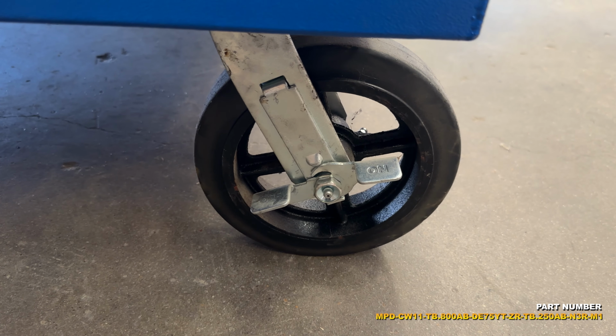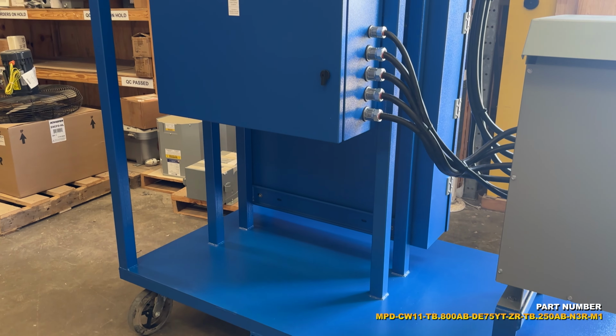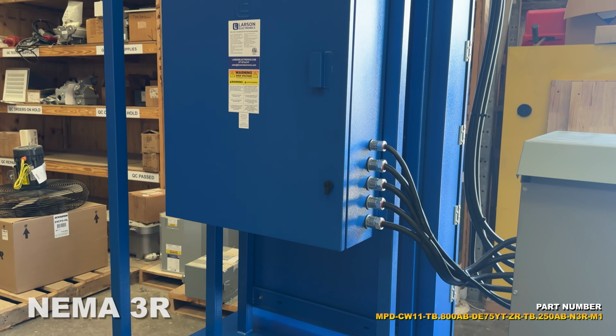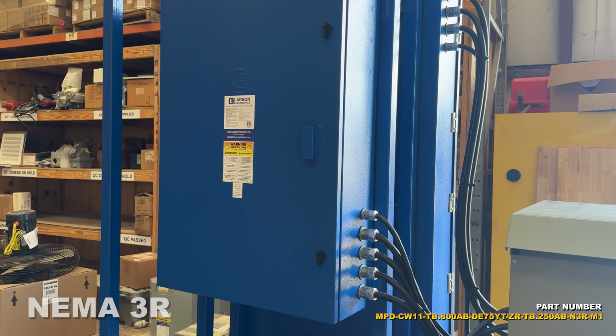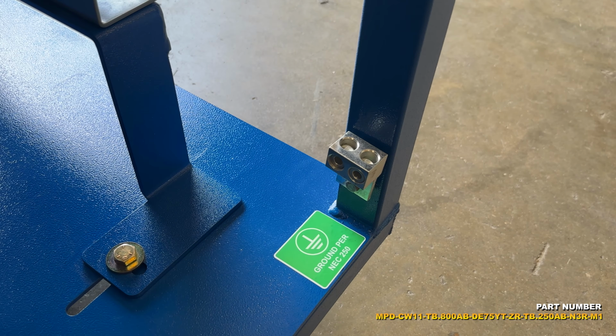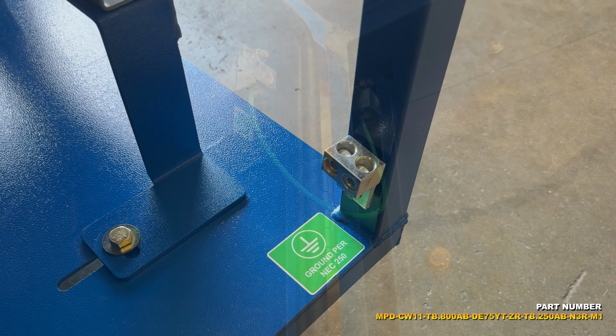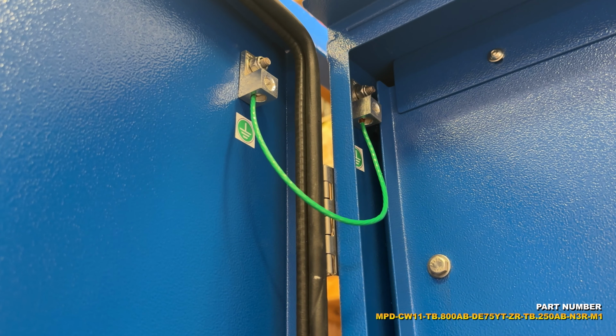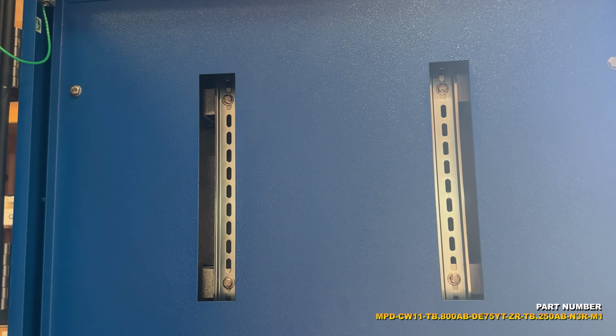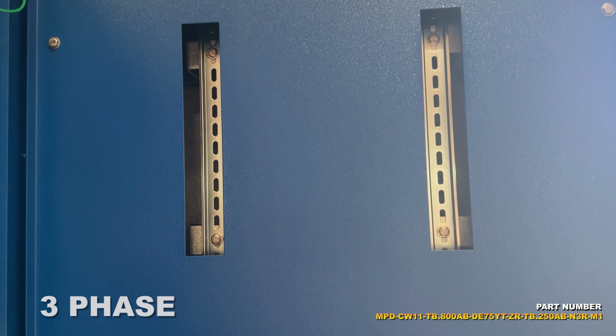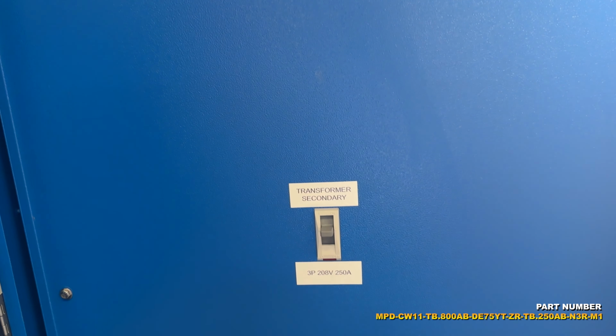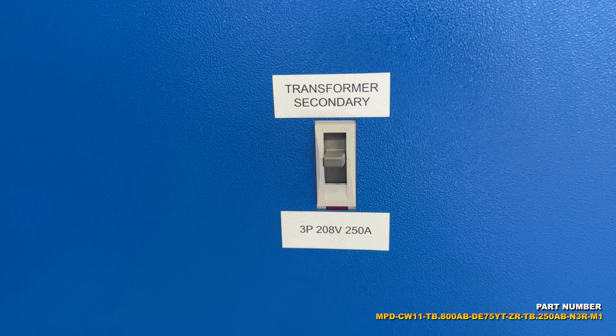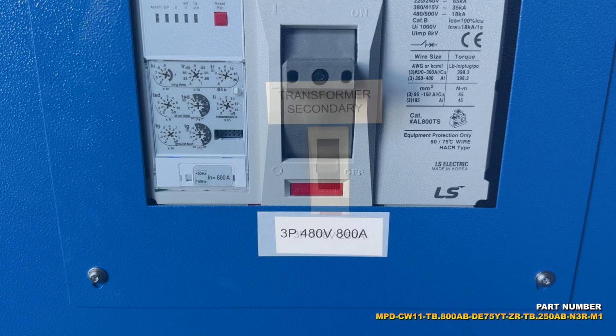A customer-provided cord brings 3-phase 480 volt power to the primary side, which is protected by an 800 amp 3-pole molded case circuit breaker and passes power to the transformer. The NEMA 3R rated transformer converts 480 volt to 3-phase 208Y or 120 volt AC at 60 Hz and passes the current to the secondary side.